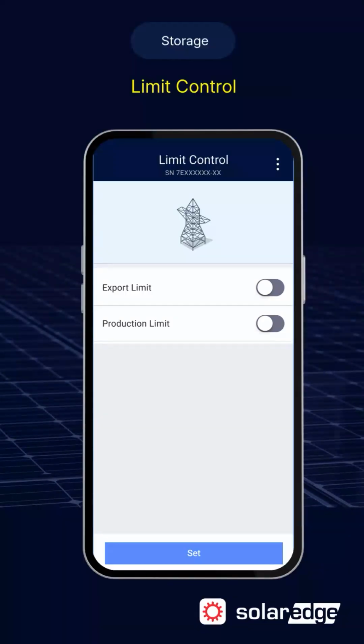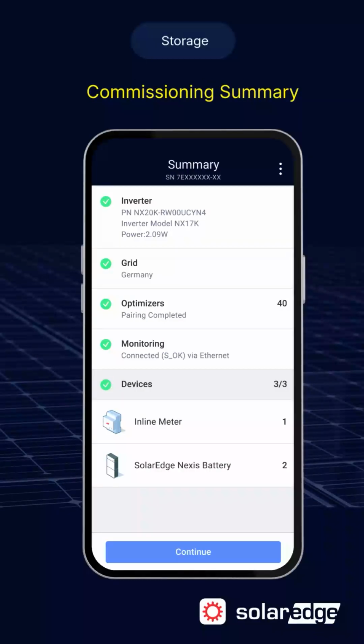If required by your local utility or grid regulations, configure export or production limits. If no limits are required, leave both options disabled. Tap Set to continue. Review the commissioning summary to verify that the entire system has been commissioned successfully. Make sure all sections display a green checkmark, including the battery and inline meter under Devices. When everything is verified, tap Continue.